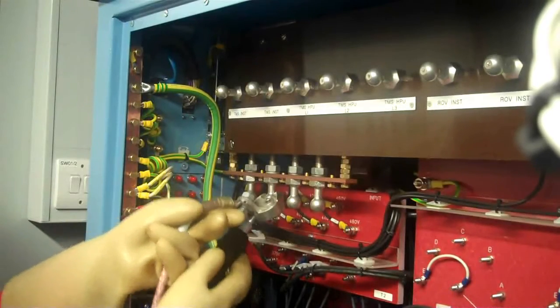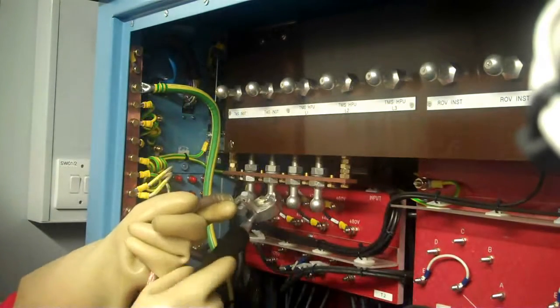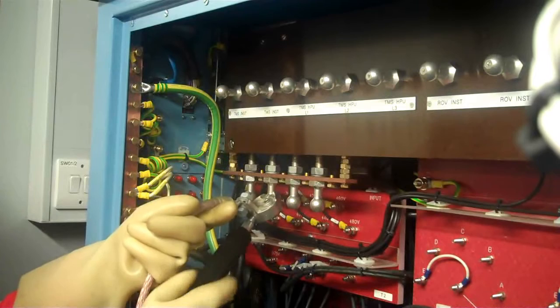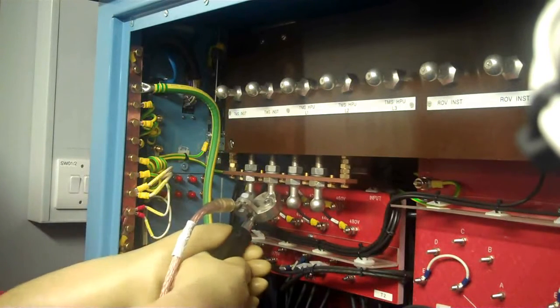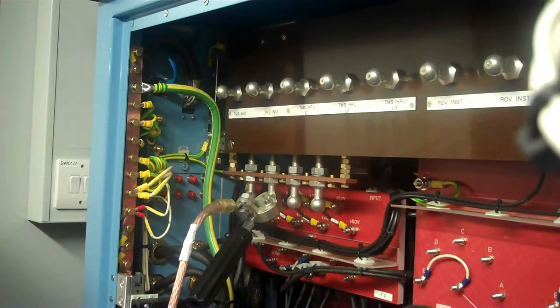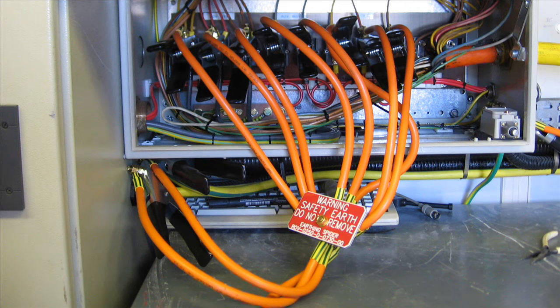The next step in this procedure is to attach additional earths to the step up transformer at the supply or surface unit. This provides an added precaution of tying the high voltage system to earth whilst the maintenance is being carried out. Some systems may use an earthing spider for this, others may use an earthing or grounding breaker.